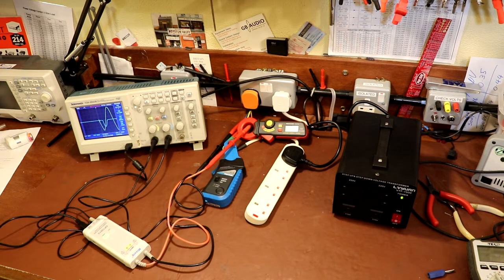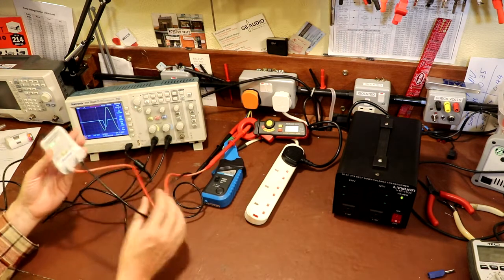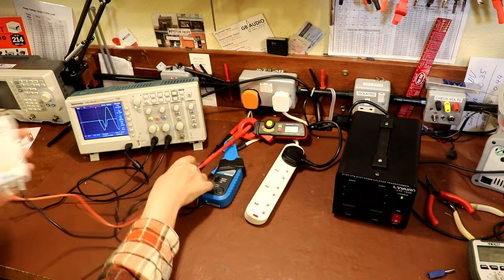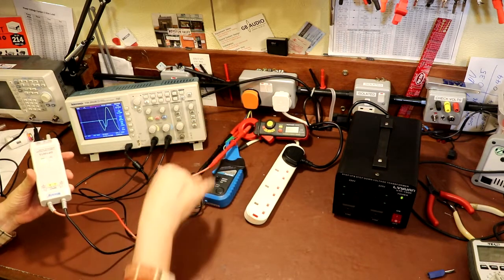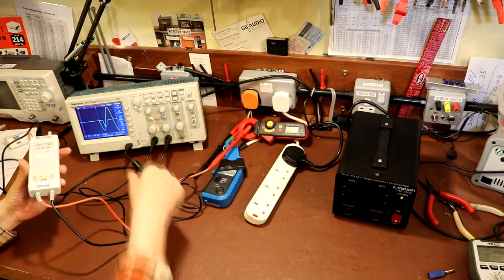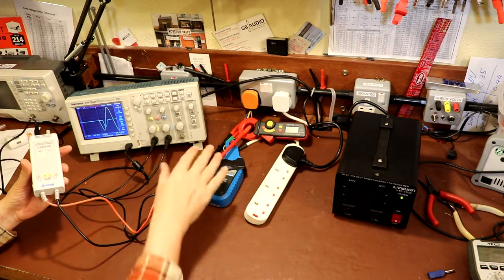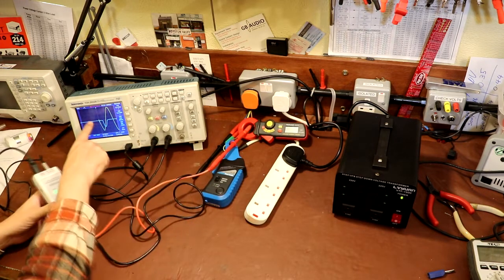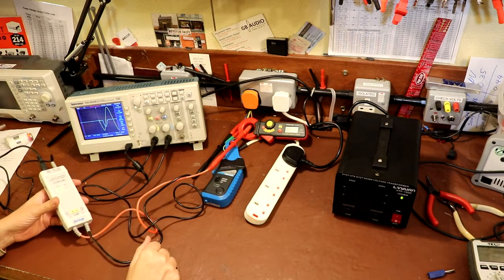Well, just for giggles, I thought it might be quite interesting to try and take a measurement of the inrush current. So what I've done is I've got our differential probe here. Apologies for the rat's nest. And this is just connected to the incoming mains supply. So we're actually supplying the transformer again with 240 volts. So the scope is showing in yellow here, that's just the incoming mains.